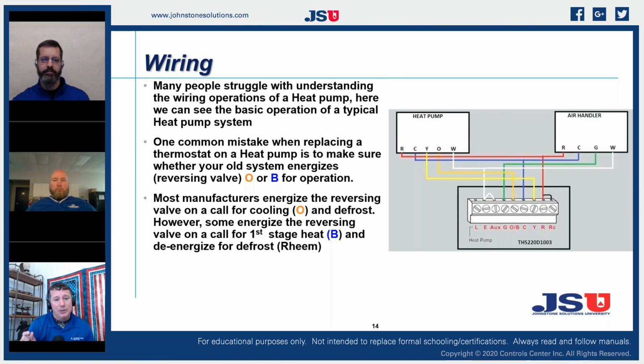Yeah. And what they are doing is their natural state is cooling. And then when it is in heating mode, they're going to energize that reversing valve. So it's the same wire. O/B is the same wire. It is our reversing valve wire. It's just done differently depending on the manufacturer of equipment. So if you are taking a thermostat off a heat pump system and replacing it with an aftermarket thermostat, they all will have that distinction of O/B. And we have to tell it what we want that terminal to be. Do we want to energize it in heating for B, or do we want to energize it in cooling for O?